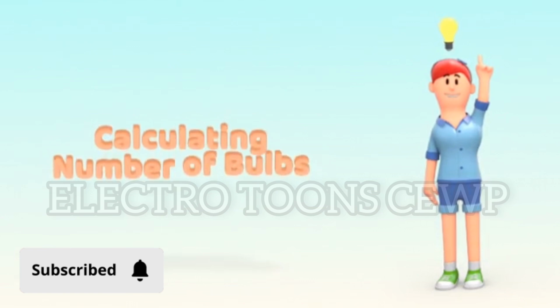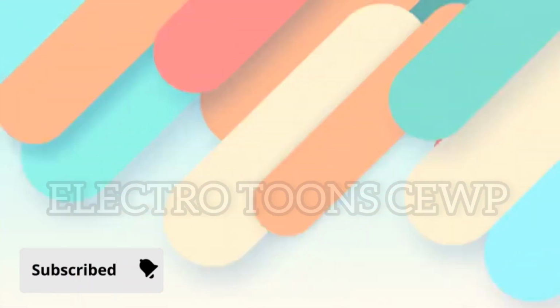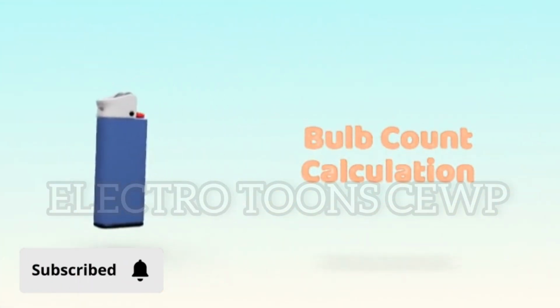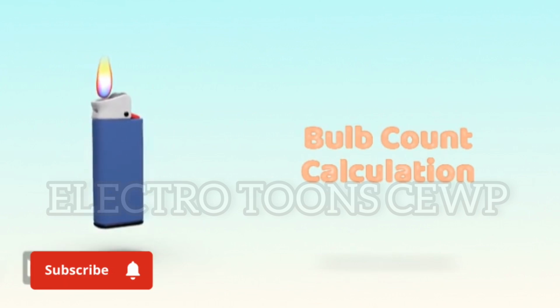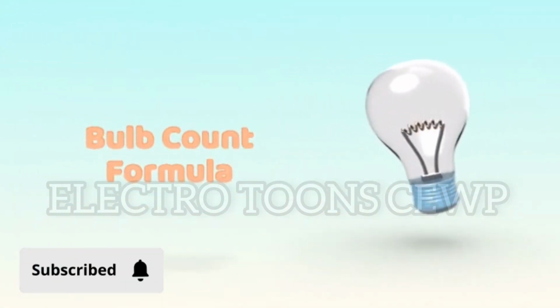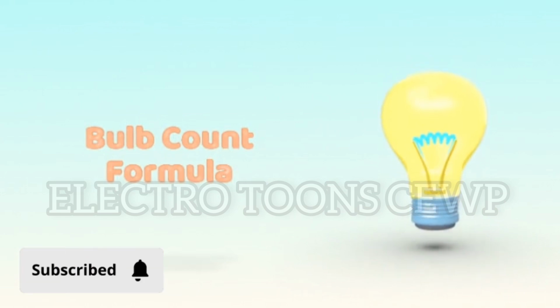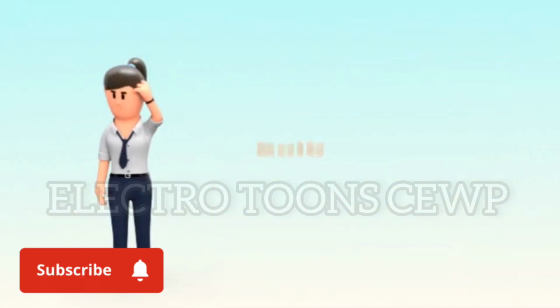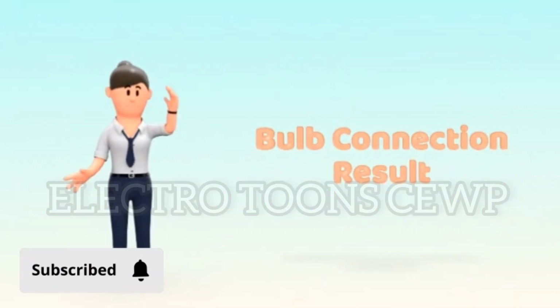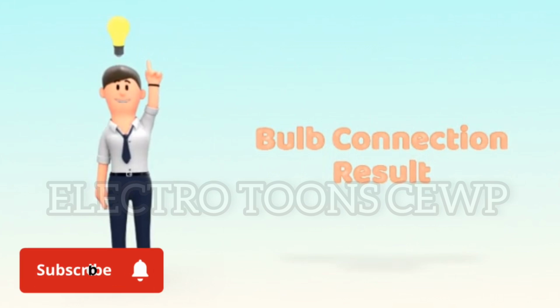2. Calculating the number of 20-watt bulbs. The total load can be used to determine how many 20-watt bulbs can safely be connected. Number of bulbs equals total load divided by 20 watts per bulb, which is about 55.2. So you can safely connect 55 bulbs of 20 watts each to the 6A circuit.